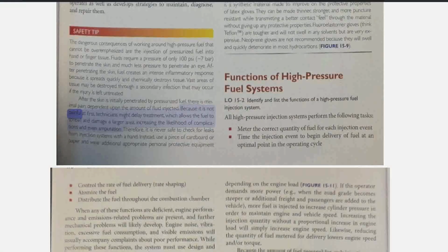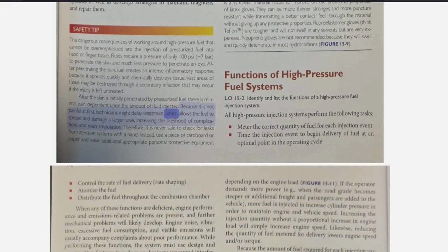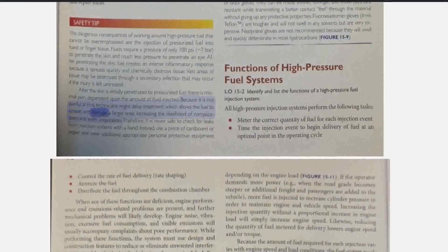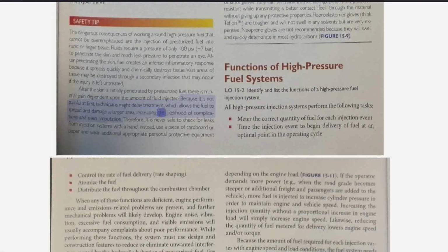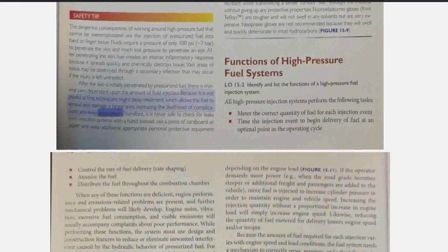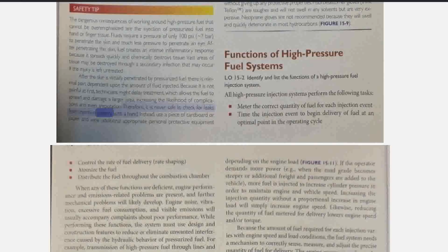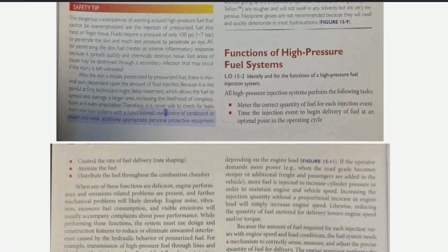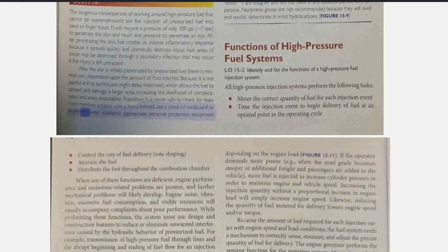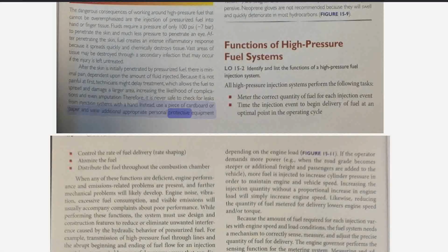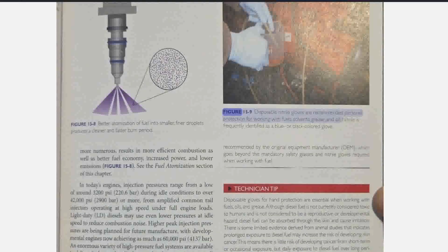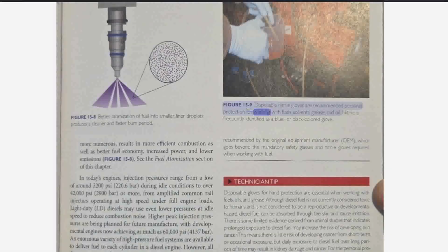Because it is not painful at first, technicians might delay treatment, which allows the fuel to spread and damage a larger area, increasing the likelihood of complications and even amputation. Therefore, it is never safe to check for leaks from injection systems with a hand. Instead, use a piece of cardboard or paper and wear additional appropriate personal protective equipment. Figure 15-9: disposable nitrile gloves are recommended personal protection for working with fuels, solvents, grease, and oil.